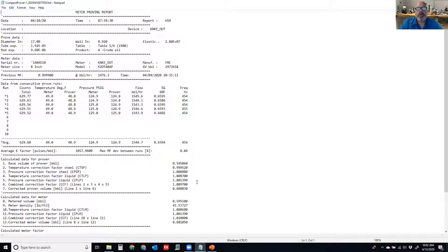We're dealing with volume here, density comes into play, and we're looking at the effects of temperature and pressure on the liquid. When we do a mass proving report, there is no correction for the liquid because it's mass — the only effect is temperature and pressure on the steel of the prover itself.